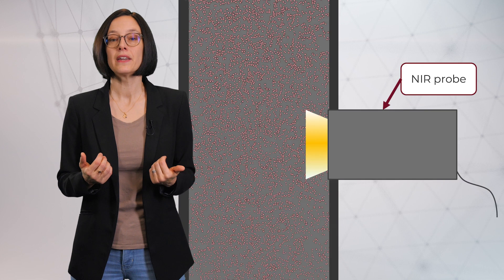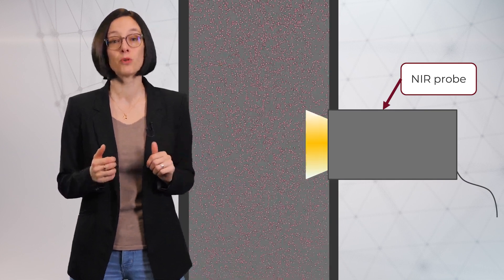Yet probe fouling is an important issue for continuous operation, since over time a layer of material can get stuck to the surface of the probe. Here we zoom into a probe installation.